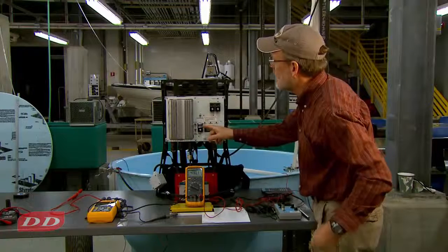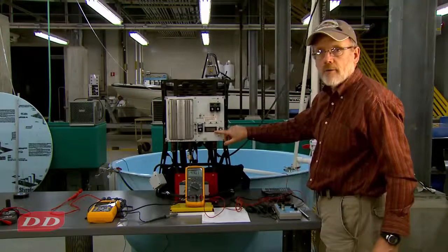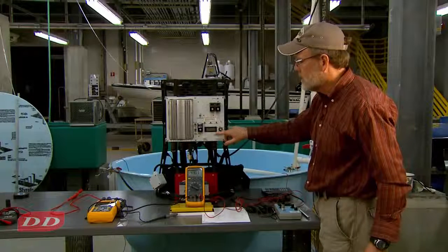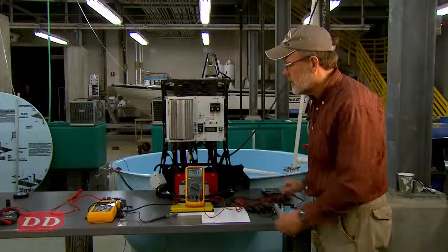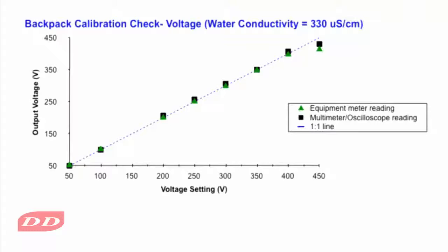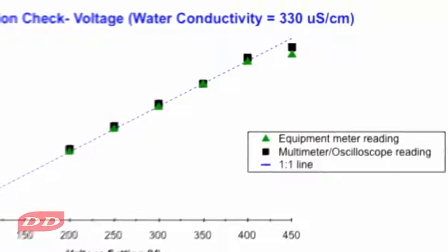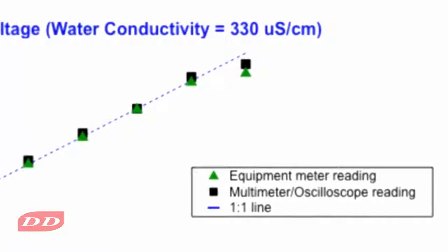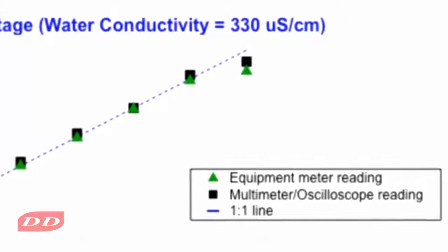So again, we dialed in 450. We only got about 419 volts, and our multimeter said it was 430. So there was some disagreement there in these readings. And then it shut off. So we're at the capacity limit of the machine.